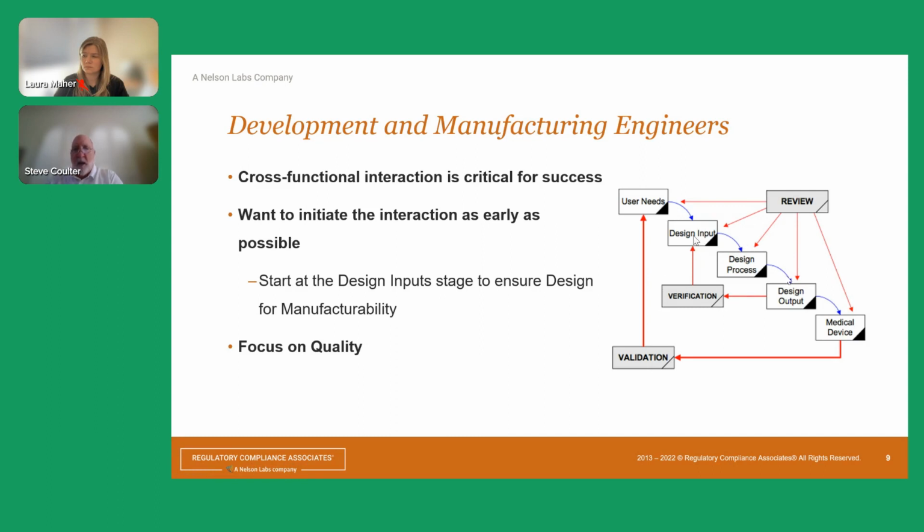Once I get the design out, the design process completed, then what we're going to do is characterize the product, the final design. This full characterization is what we're going to be talking about in the DMR and the design transfer process. These outputs are the characterization of the final product. And then you take that and we just call it medical device. This is the transfer. This is when you go to commercialization, go to manufacturing.